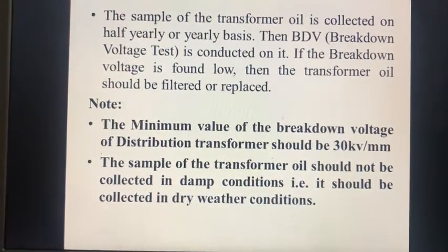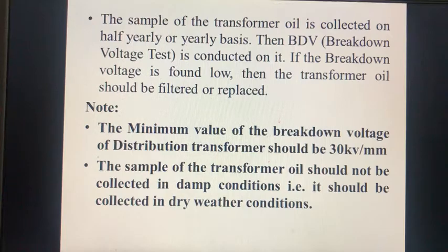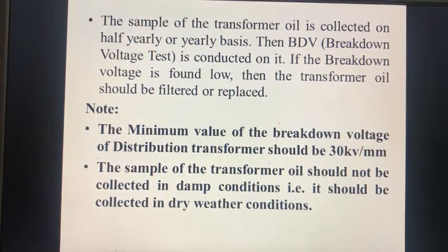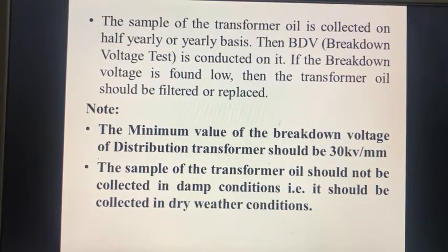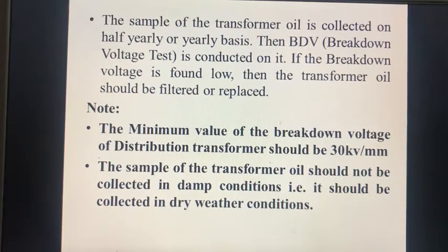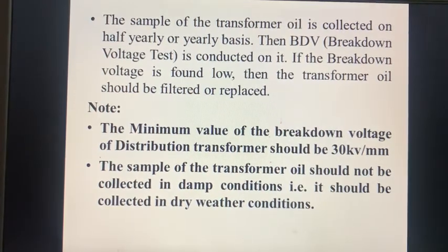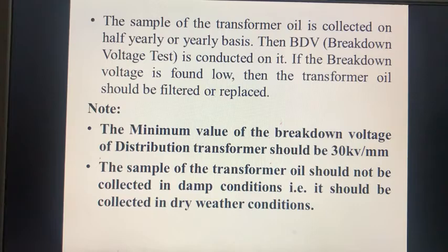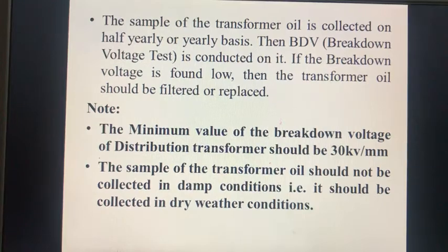The sample of the transformer oil is collected on half yearly or yearly basis. The sample of the oil is collected to check its breakdown voltage. Breakdown voltage is basically a dielectric strength test of the transformer oil. It should be conducted on half yearly or yearly basis.